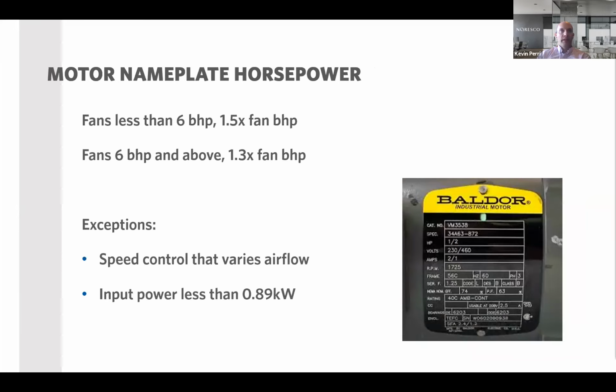All right, motor nameplate horsepower. This isn't new, if you're familiar with it, but they added 2 exemptions. Exemption 1 is for fans equipped with electronic speed control devices. And exception 2 is for fans less than 0.89 kilowatts of power. So you still have to follow the motor nameplate horsepower requirements for your motors, but if they're equipped with speed control or draw less power, then they're exempt from having to follow that 1.5 times the fan brake horsepower or the 1.3 times fan brake horsepower.